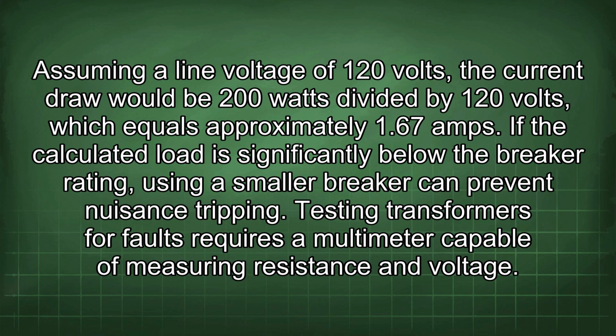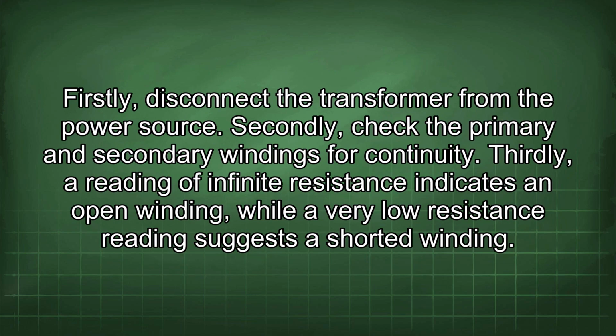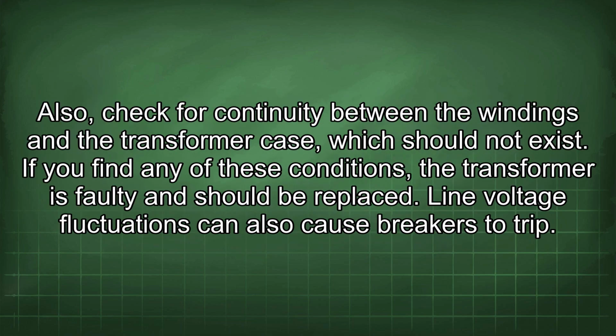Testing transformers for faults requires a multimeter capable of measuring resistance and voltage. Firstly, disconnect the transformer from the power source. Secondly, check the primary and secondary windings for continuity. Thirdly, a reading of infinite resistance indicates an open winding, while a very low resistance reading suggests a shorted winding. Also, check for continuity between the windings and the transformer case, which should not exist. If you find any of these conditions, the transformer is faulty and should be replaced.